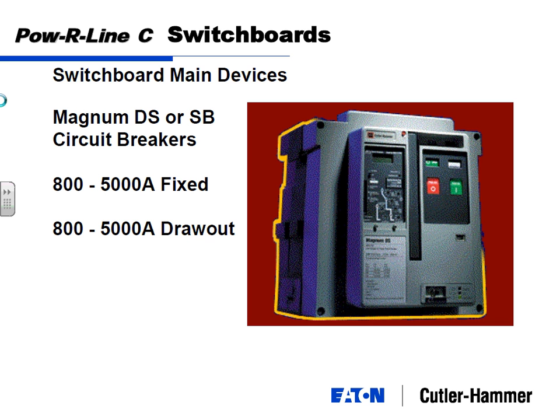But it's the same standard as molded case circuit breakers. And there are different standards in testing. But the molded case circuit breaker standard is designed to be installed in switchboards. So when you're talking a switchboard with molded case circuit breaker feeders, you would more than likely use a Magnum SB insulated case circuit breaker.